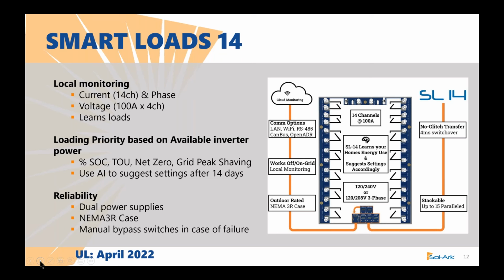Yeah, it's actually a 200 amp AC bus. That means we can pass through 200 amps or 48 kilowatts worth of power, depending on what sources you have that come from. So yes, it'll have a 200 amp AC bus, but we still have our internal transfer switch, which disconnects us from the grid and isolates the load output of the inverter. So there's no need for an external transfer switch. We are rated for 200 amps of pass through.